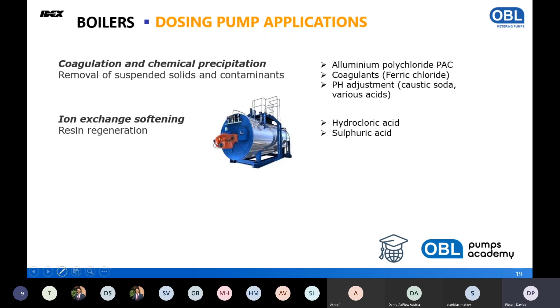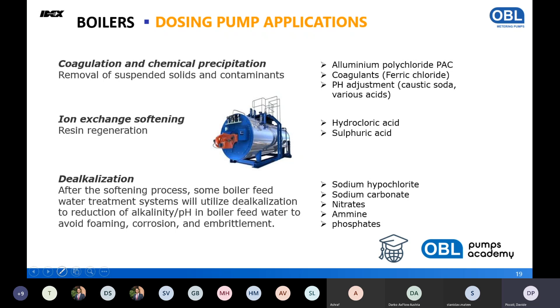At the end, after the softening process, some boiler feed water needs to be treated with dealkalization to reduce alkalinity and pH. And again, you see sodium hypochlorite, but also sodium carbonate, nitrates, amine, phosphates. In the past, it was very, very useful to use hydrazine, but now I think it's forbidden by law due to the possibility of causing cancer. Phosphates are very, very often used in this process. So the process of the boiler feed water is very complicated, but the most important part is dealkalization. So where you will see pumps used, especially in chemical injection packages, is to inject these amine, phosphate, nitrates, and sodium carbonate.